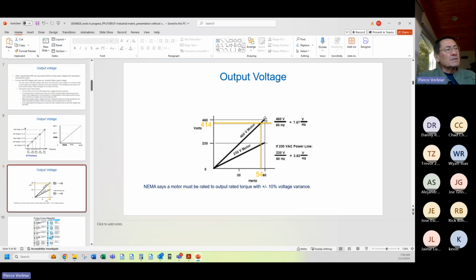NEMA says that a motor must be rated to operate at its output rated torque with a plus or minus 10% voltage variance. Now, 10% reduction on 460 is 414 volts, which is less than the voltage drop across the matrix drive. But we'll use 10% just to be conservative. If the voltage drop across the matrix drive with a 460 volt input is 10%, then we're going to put a maximum of 414 volts into that motor.